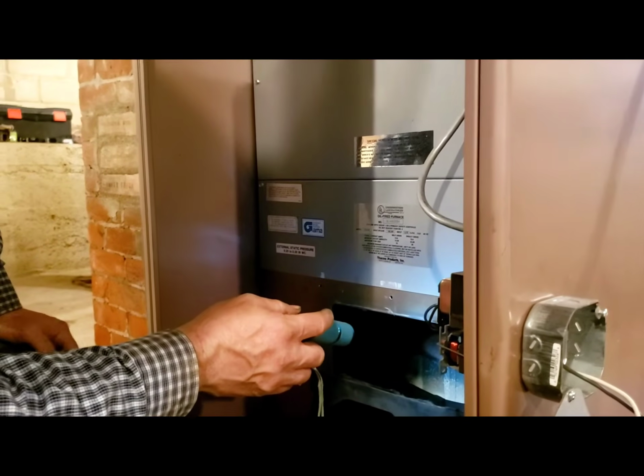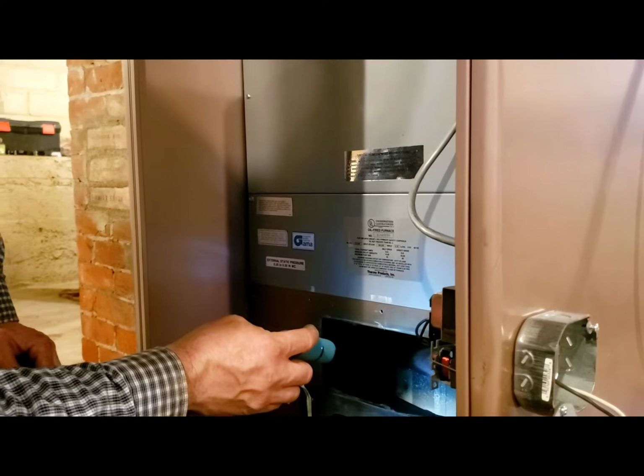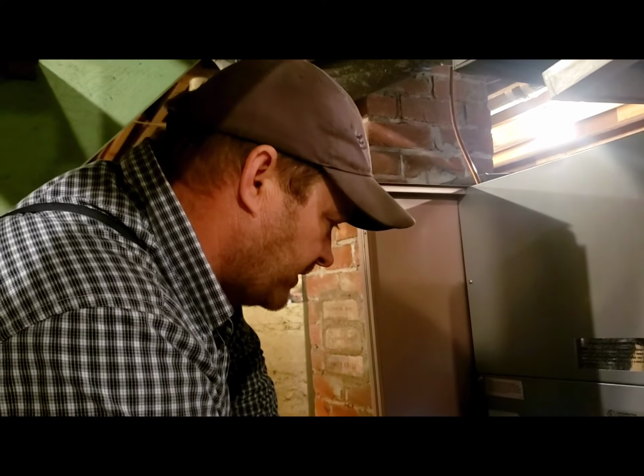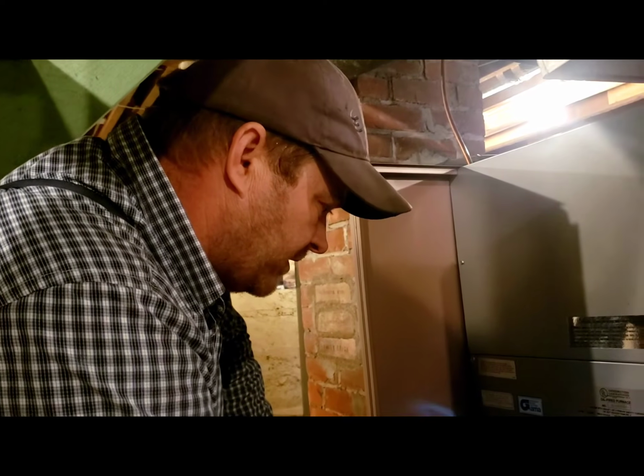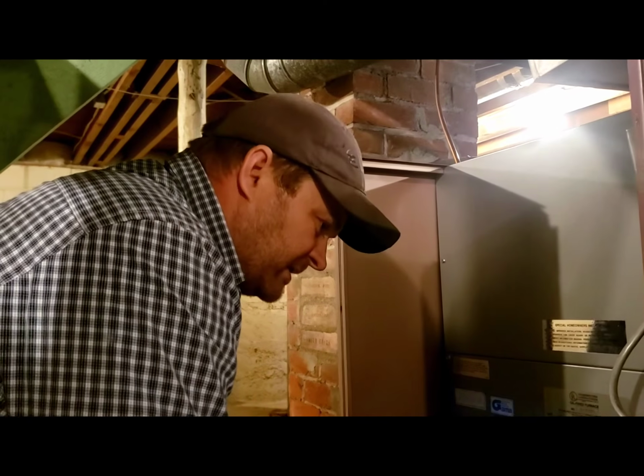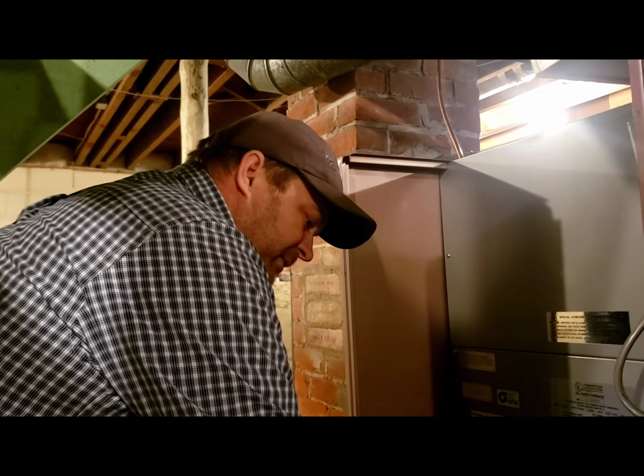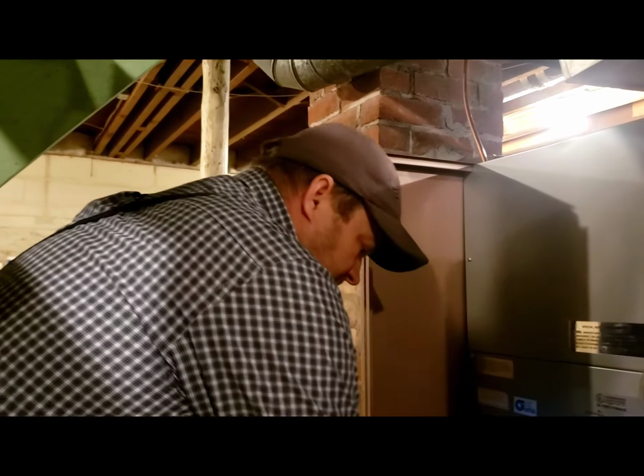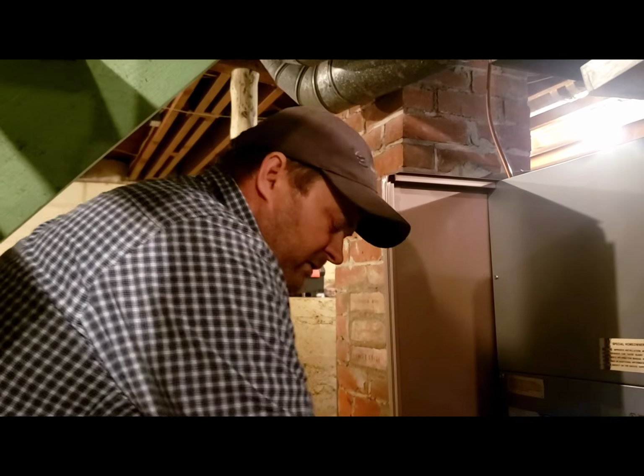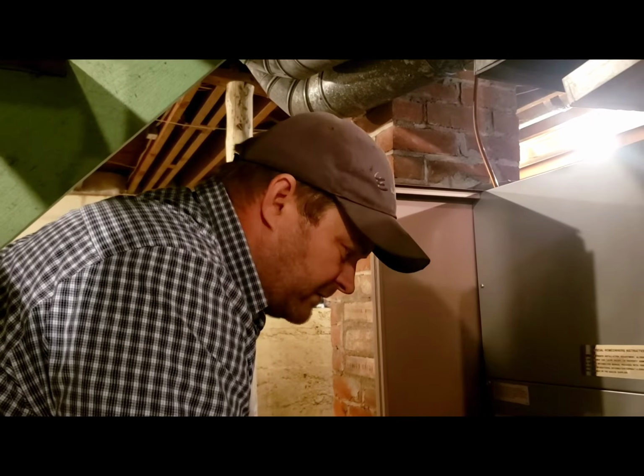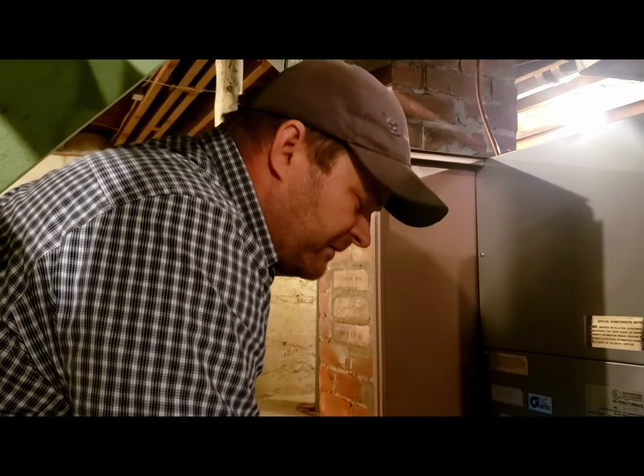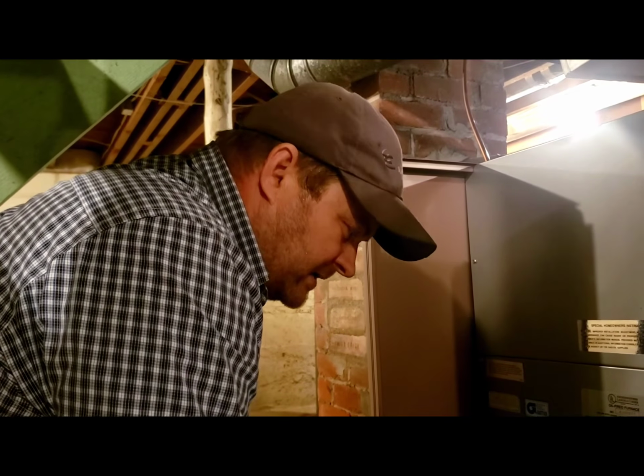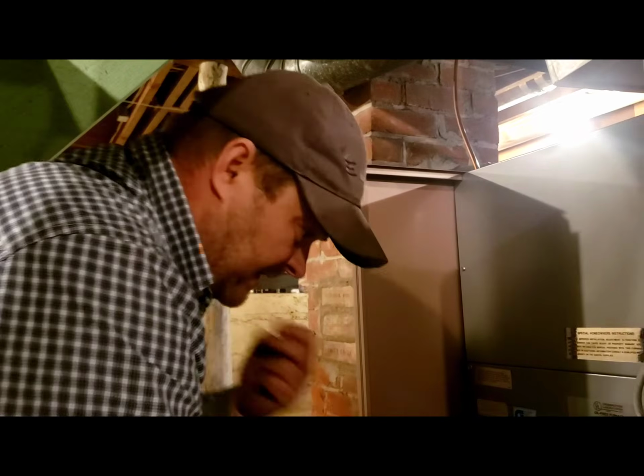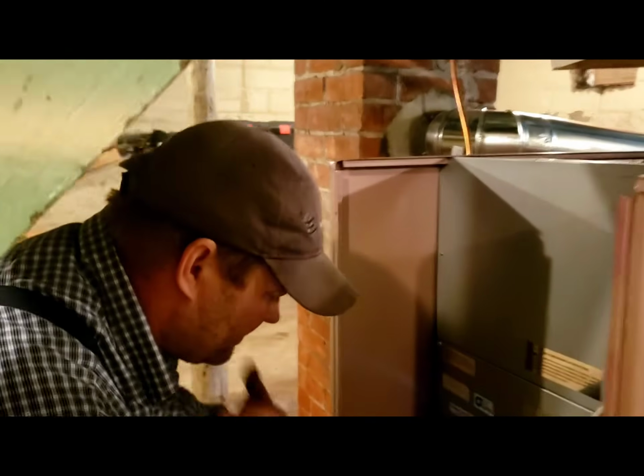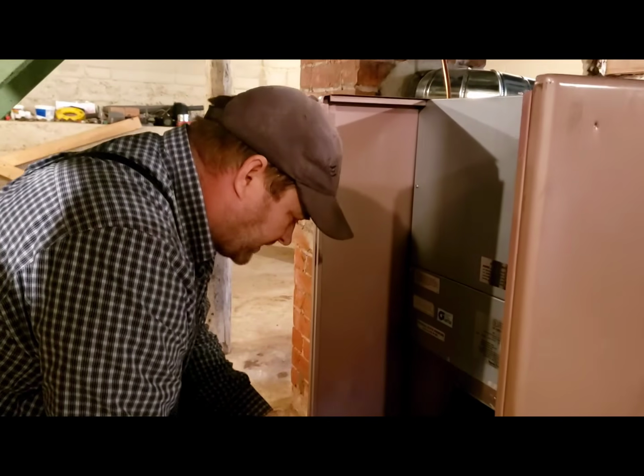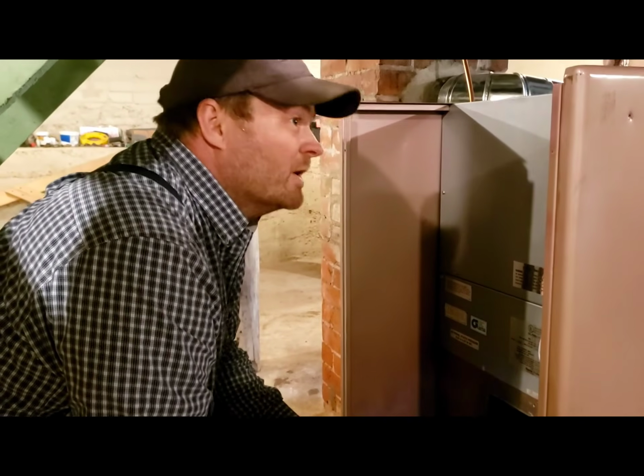Every Thermopride we've ever had had this, but for some reason, when we got this one, it was in pieces. This was off the burner, the pump was off, the burner was out, the plates were off, everything was gone. So somebody had it apart, couldn't figure it out, gave up on it, and now I'm putting it all back together properly. What it ended up being was a bad pump, that was their problem.